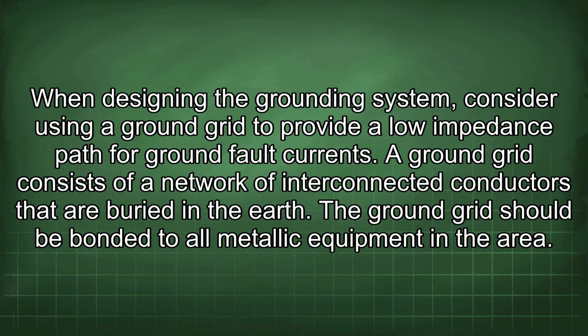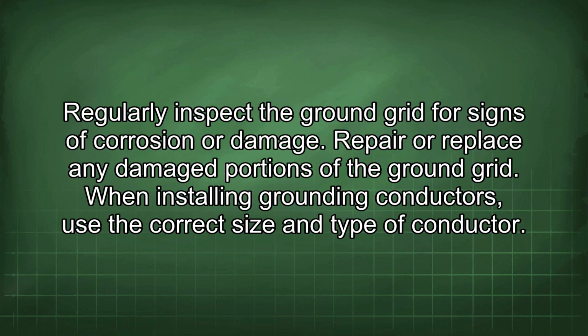A ground grid consists of a network of interconnected conductors that are buried in the earth. The ground grid should be bonded to all metallic equipment in the area. Regularly inspect the ground grid for signs of corrosion or damage. Repair or replace any damaged portions of the ground grid.